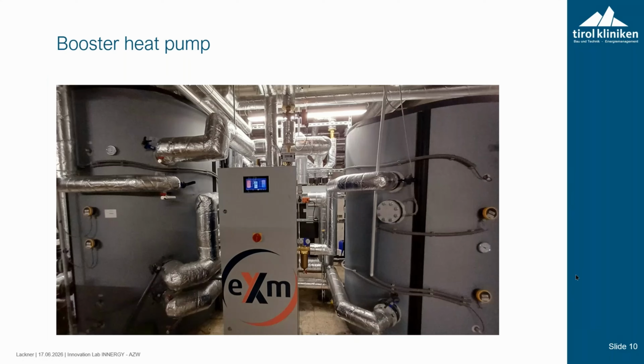We installed a new water system, and therefore we used a booster heat pump. The ground temperature will be produced by a normal heat pump, so about 45 degrees, and the boost to the warm water temperature will be done by the booster heat pumps. So we have large buffers beside it to store the water.